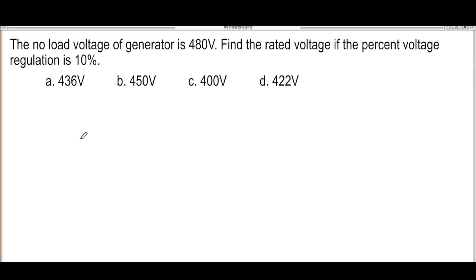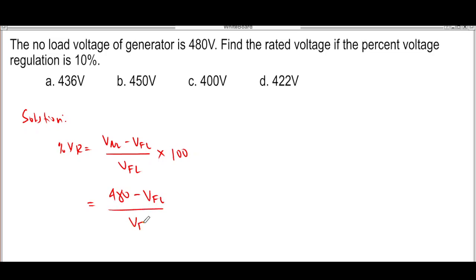Okay. So we have another problem. So the no load voltage of a generator is 480 volts. To find the rated voltage if the percent voltage regulation is 10%. Okay, so solution. So you could also put your answer in our box again if you are able to solve the problem. Okay. Over VFL times 100. So we have the no load voltage is 480, no? Minus our VFL over our VFL. Then we have times 100.